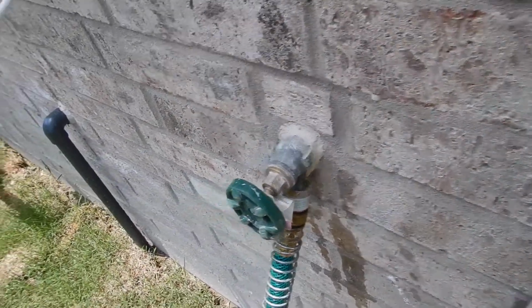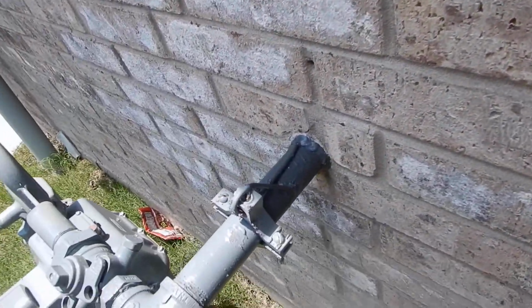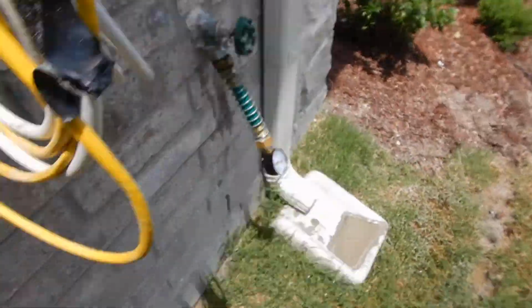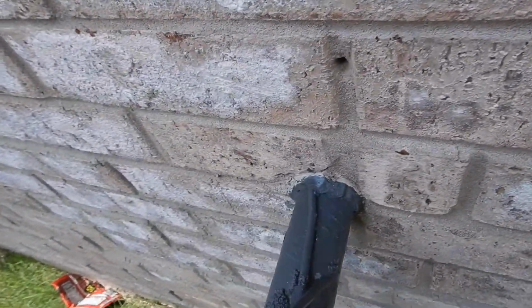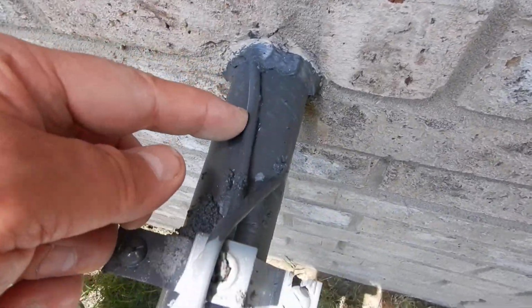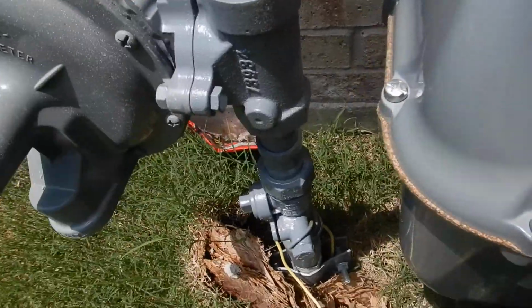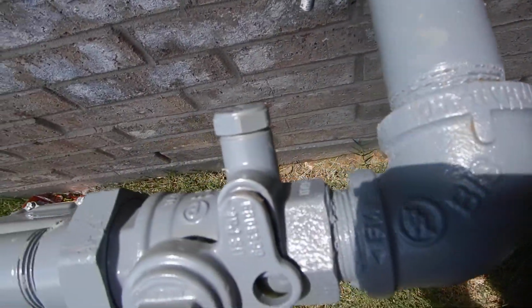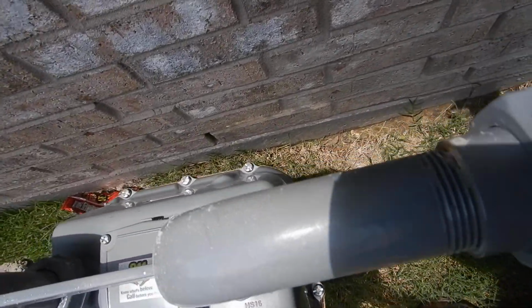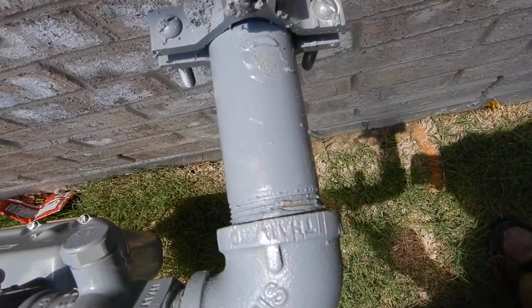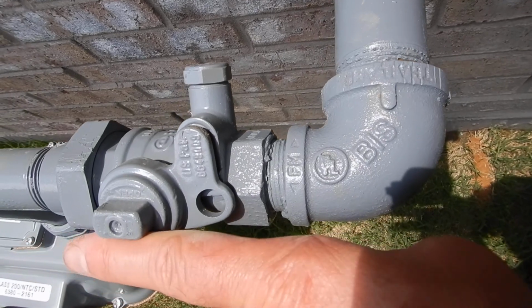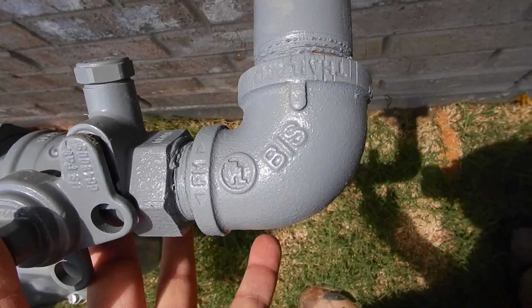About 45 psi. This is the gas meter on the east side of the garage, as I mentioned before. As I just got through mentioning. Okay. This is the bonding, the electrical bonding for the gas system. That's a good thing. And this is the main shutoff valve. This is actually your main shutoff valve, and you can shut them both off, isolated. Okay, parallel is on and perpendicular is off.